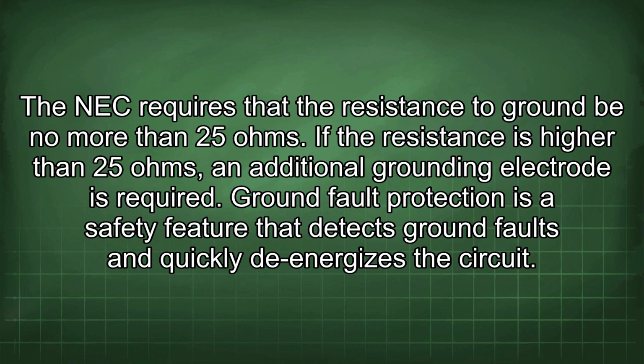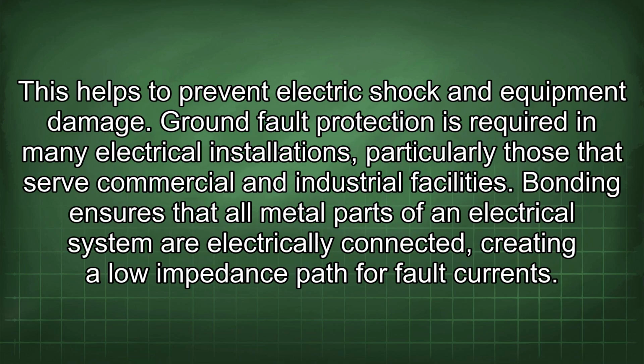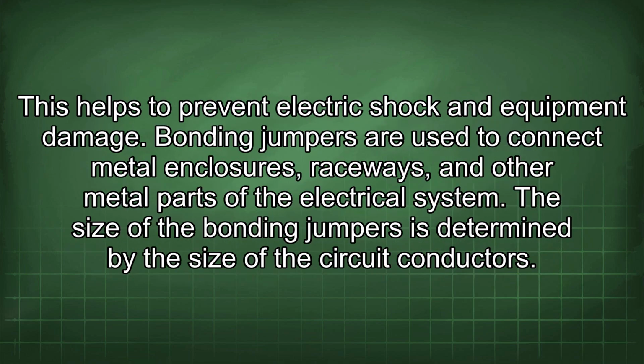Ground fault protection is a safety feature that detects ground faults and quickly de-energizes the circuit. This helps to prevent electric shock and equipment damage. Ground fault protection is required in many electrical installations, particularly those that serve commercial and industrial facilities. Bonding ensures that all metal parts of an electrical system are electrically connected, creating a low impedance path for fault currents. This helps to prevent electric shock and equipment damage.